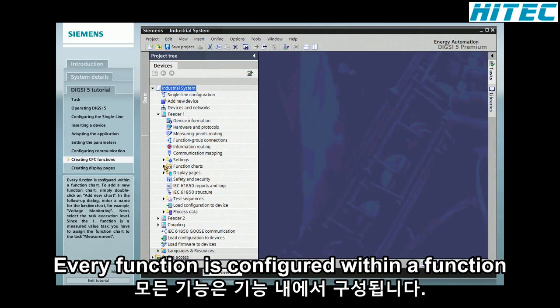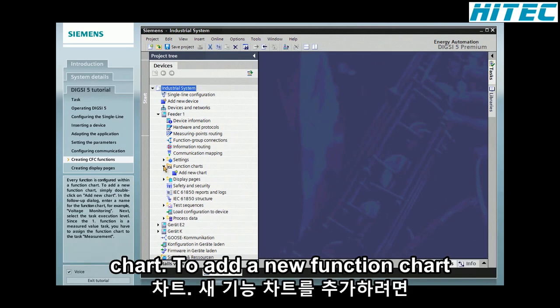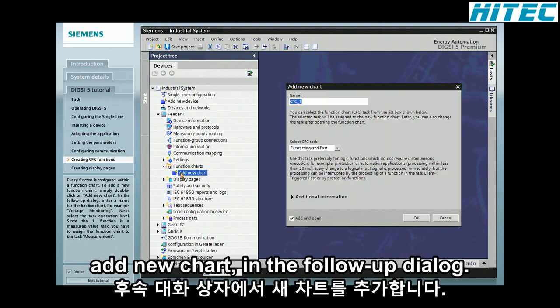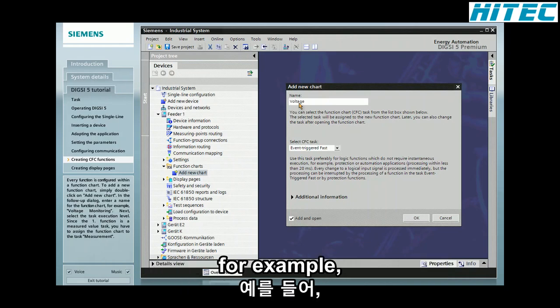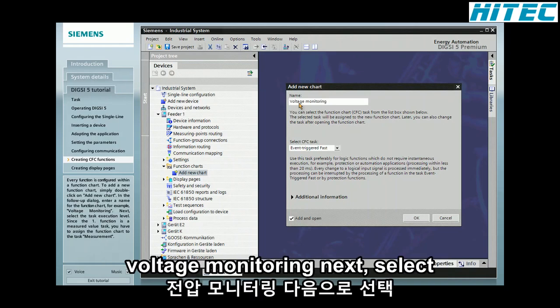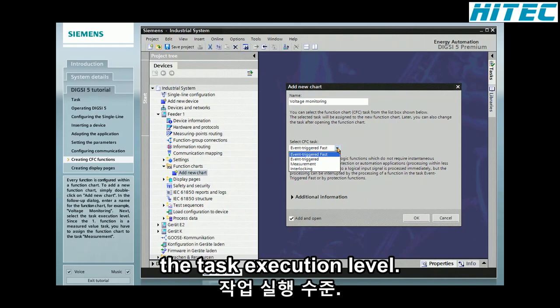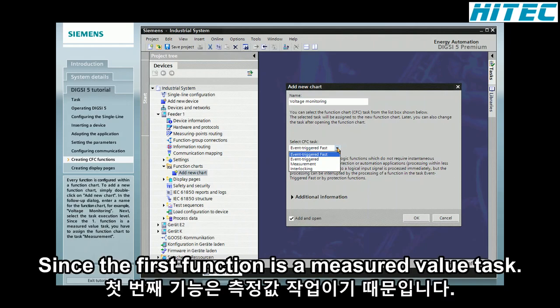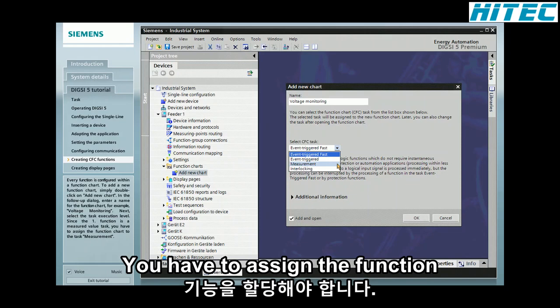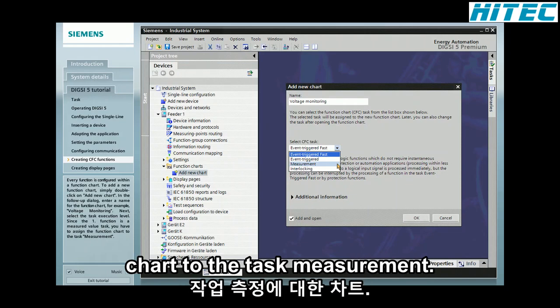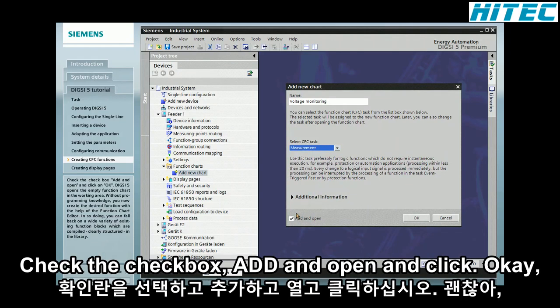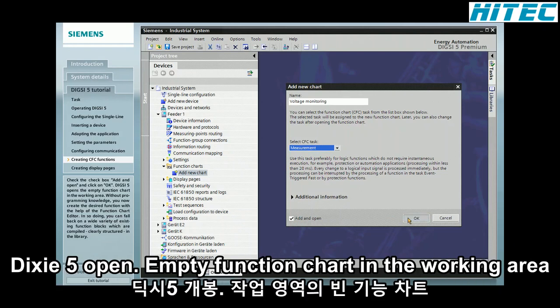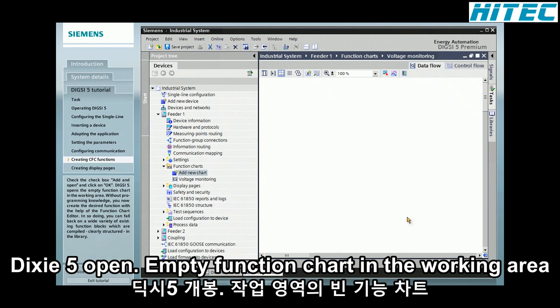Every function is configured within a function chart. To add a new function chart, simply double-click on Add New Chart. In the follow-up dialog, enter a name for the function chart, for example, Voltage Monitoring. Next, select the task execution level. Since the first function is a measured value task, you have to assign the function chart to the task measurement. Check the checkbox Add and Open and click OK. DIGSI 5 opens the empty function chart in the working area.